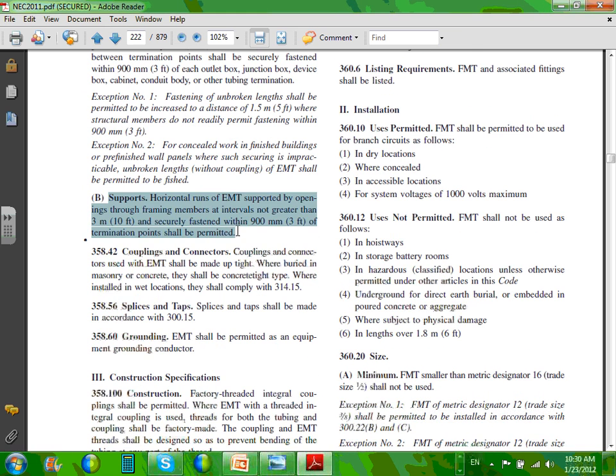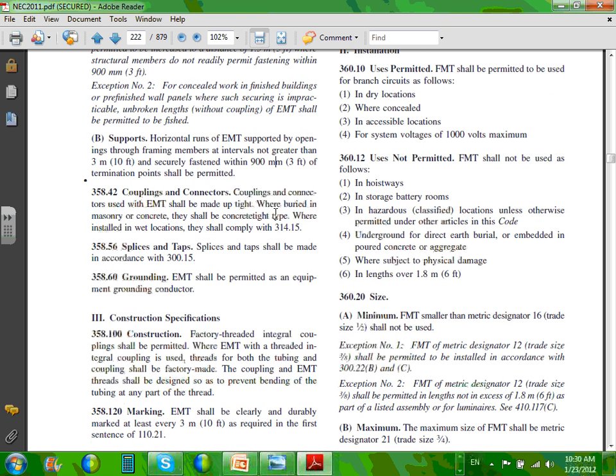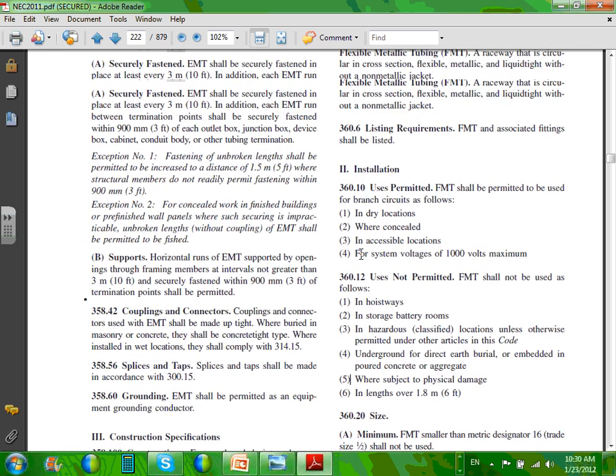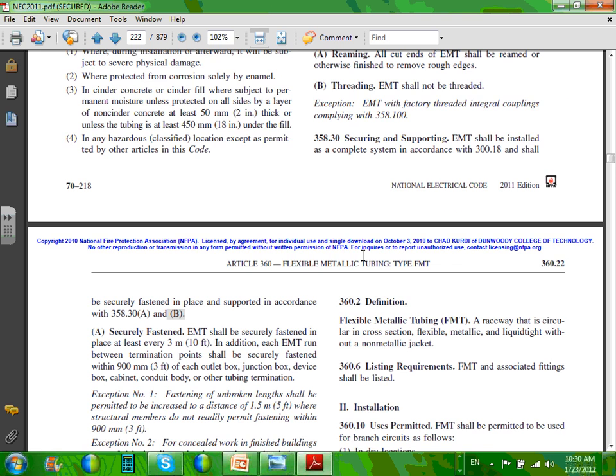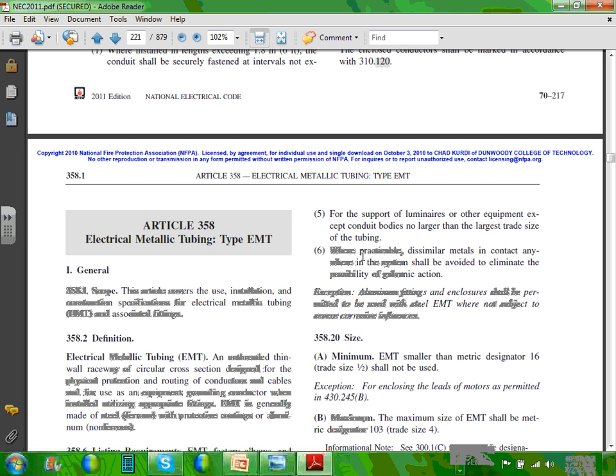Here's my support, guys. Very interesting. Support every 10 feet intervals and within 3 feet from every box. Here's my 10 feet interval and every 3 feet from every box. Grounding, can I use this conduit as a grounding? Yep. Why can you use it as a grounding? Because it says it shall be permitted as an equipment grounding conductor. Any questions, guys, about these conduits?